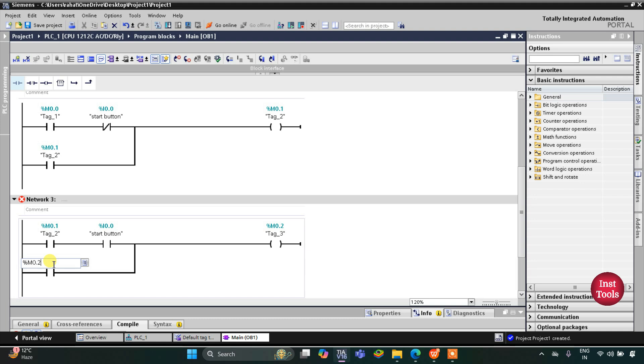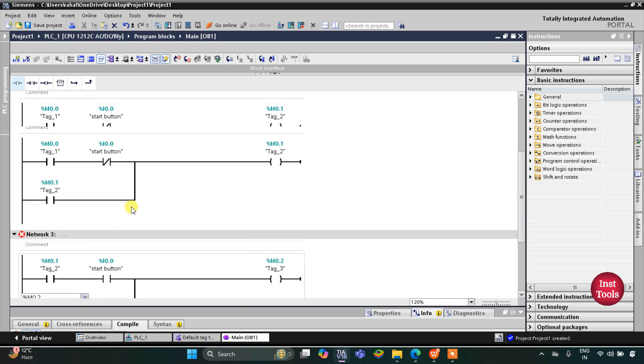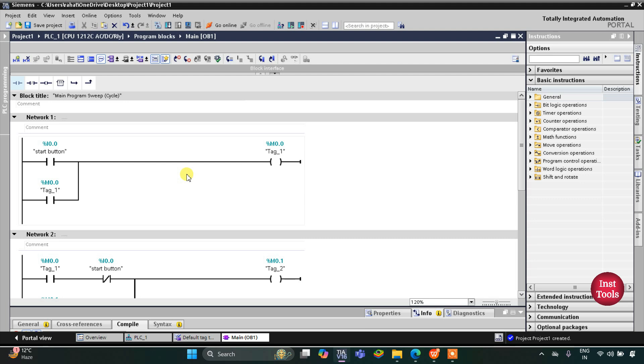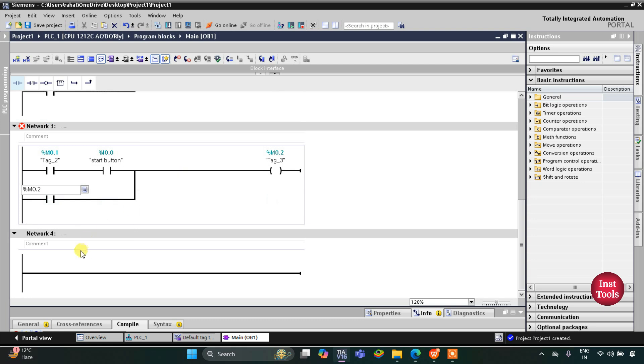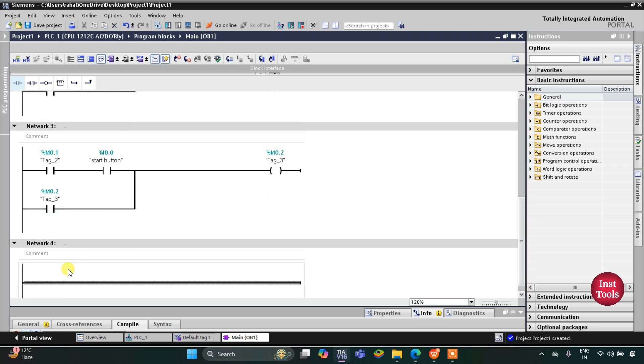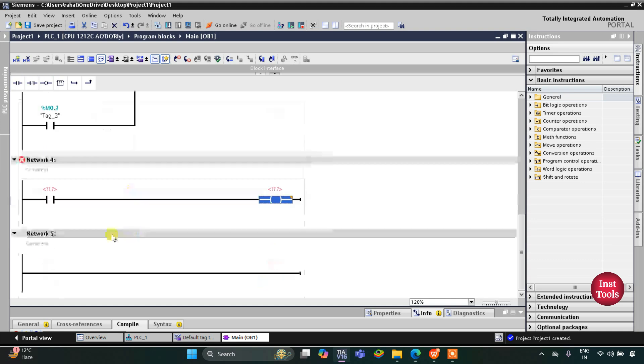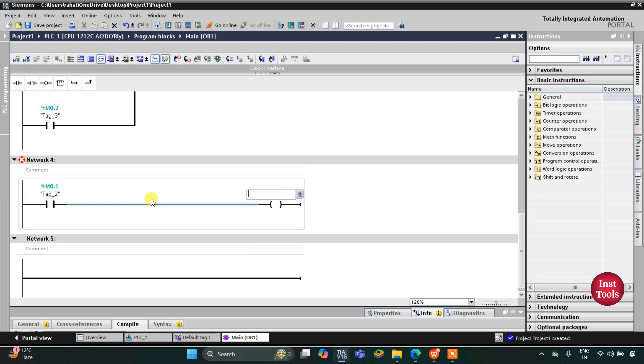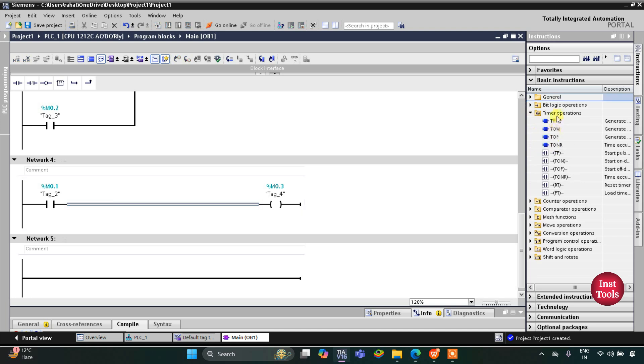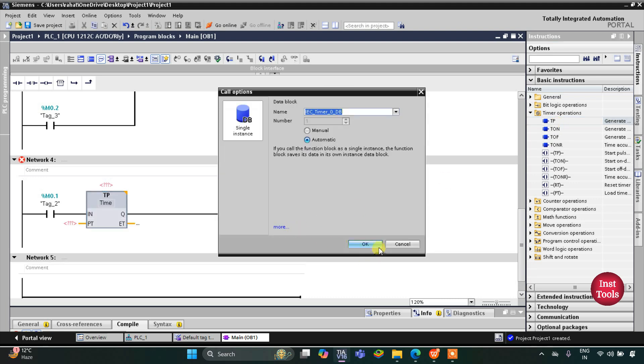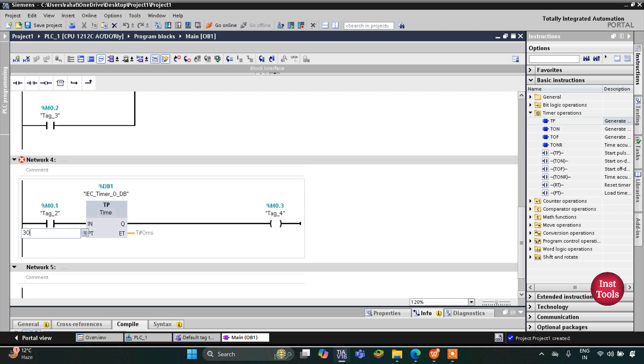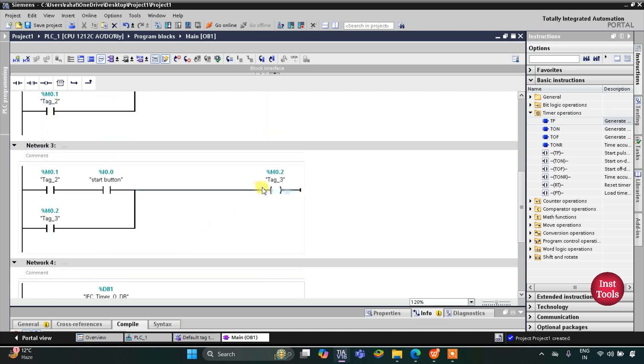M0.2 will be used to open the curtains for another 30 seconds. We will use network 4, then insert M0.1 and a coil — this coil will be M0.3. M0.3 will be turned on for only 30 seconds, so we will use a timer operation TP here set to 30 seconds.